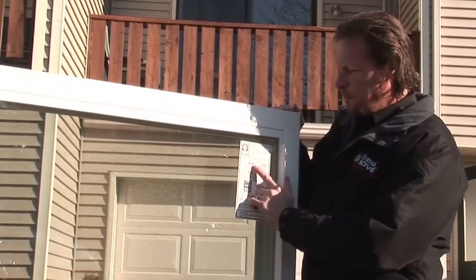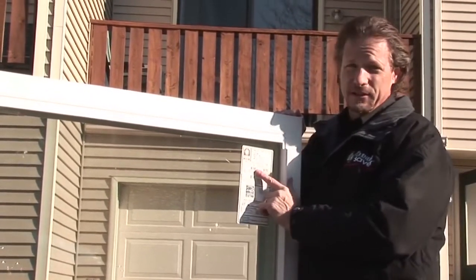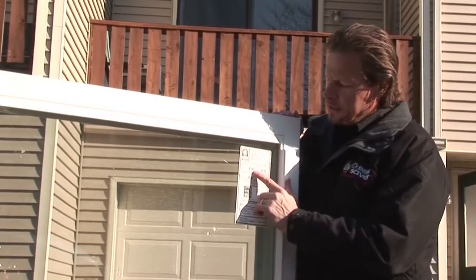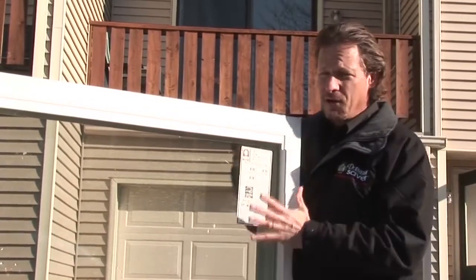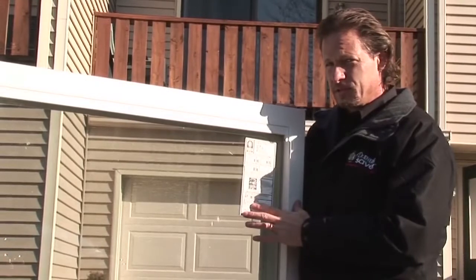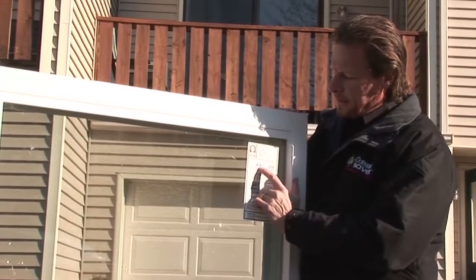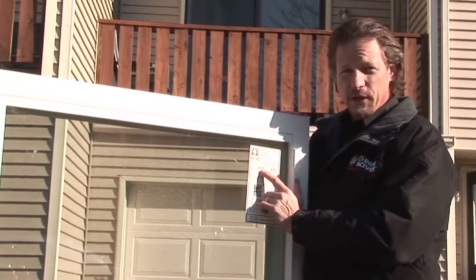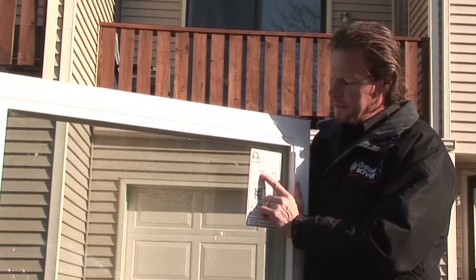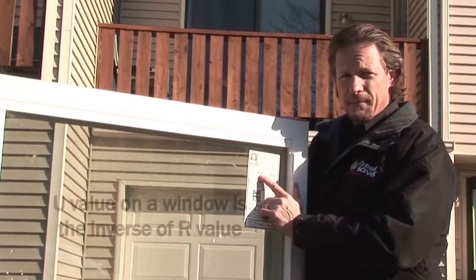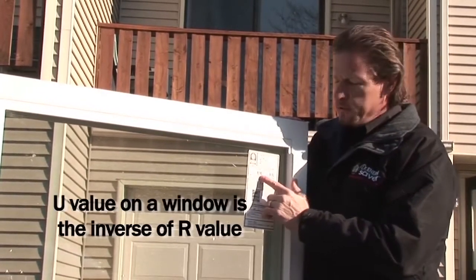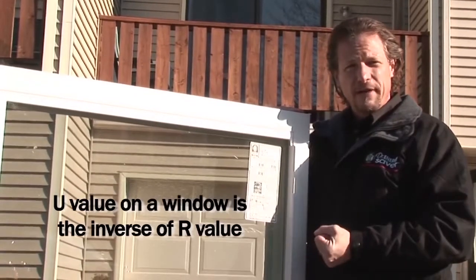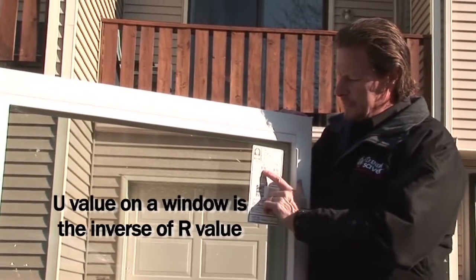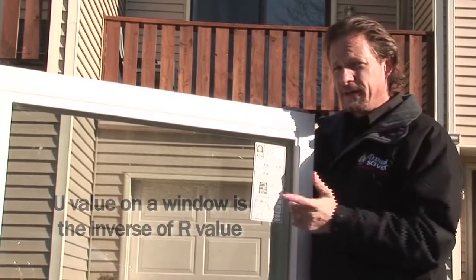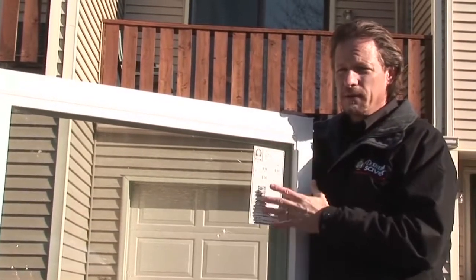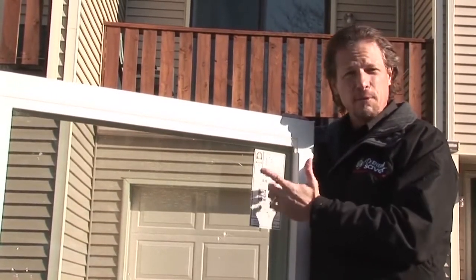But the important rating is the U factor on this window. And the U factor measures how overall energy efficient this window is. And this U value is 0.3, which is very good, very efficient window. The U value is the inverse of R value. So if we take 0.3 and divide it into 1, we get 3.33.